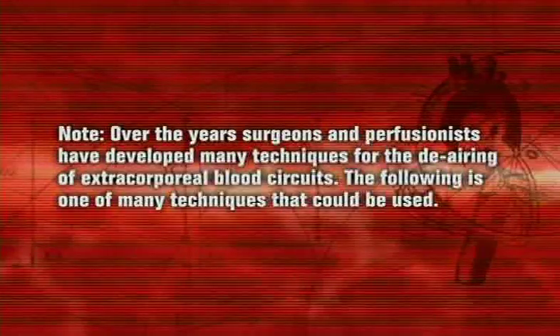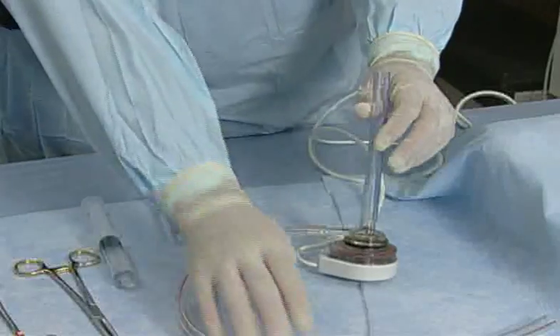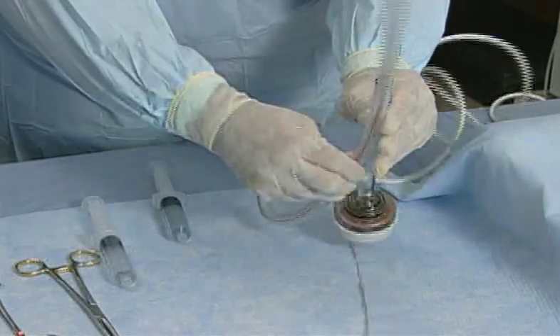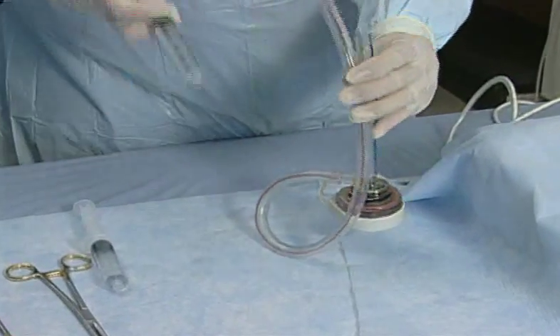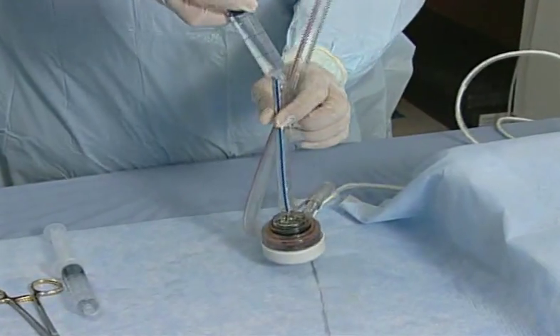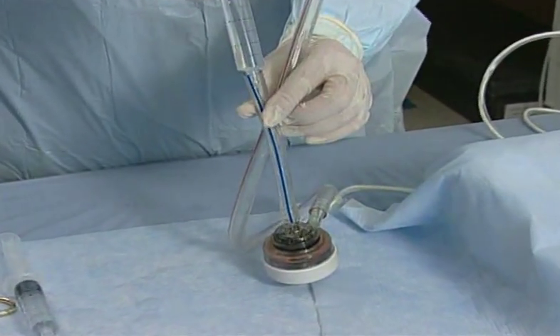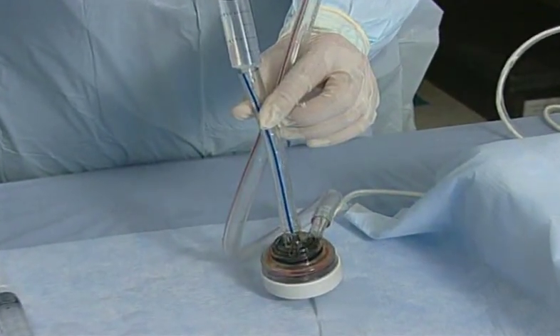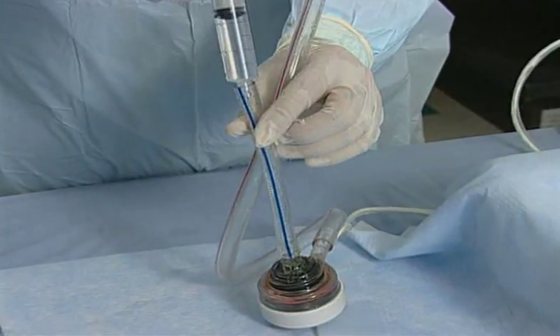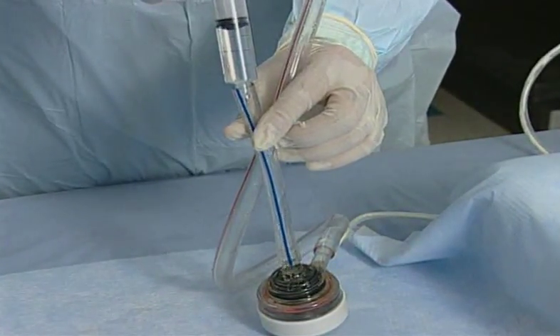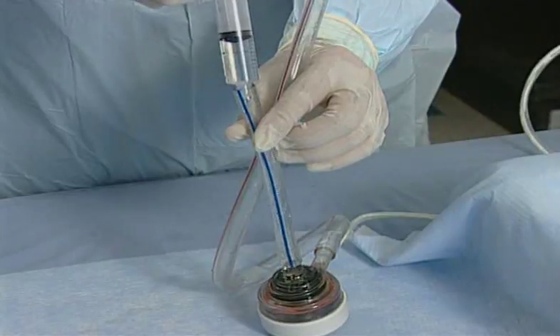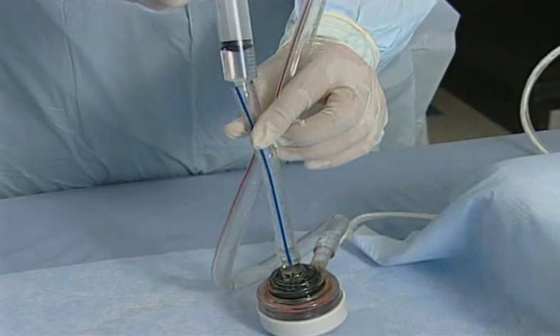Note, over the years, surgeons and perfusionists have developed many techniques for the de-airing of extracorporeal blood circuits. The following is one of many techniques that could be used. Hold the TandemHeart pump by the inflow, blue, and outflow, red pump tubing. Slowly fill the pump inflow tubing, blue, using a syringe or an Asepto with saline from the sterile field. Note, while slowly filling the pump inflow tubing, blue, the pump and pump outflow tubing, red, will also start filling up.